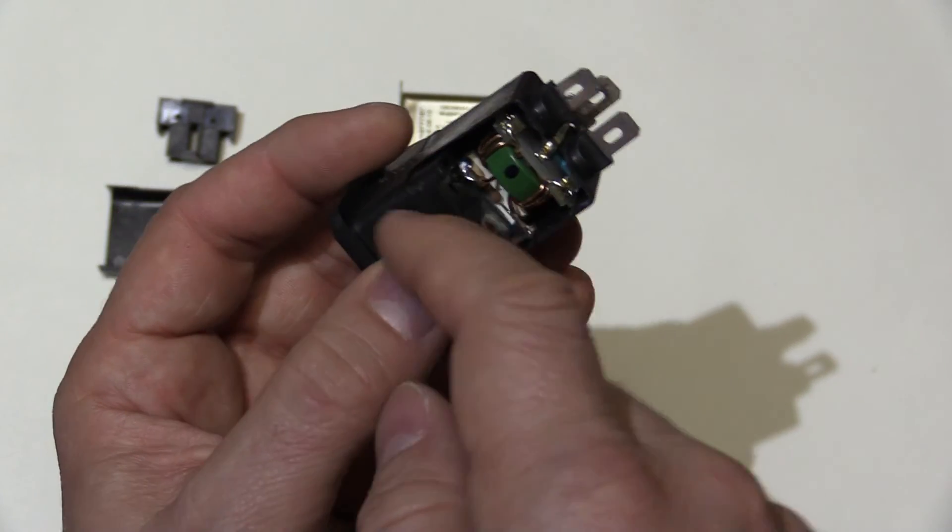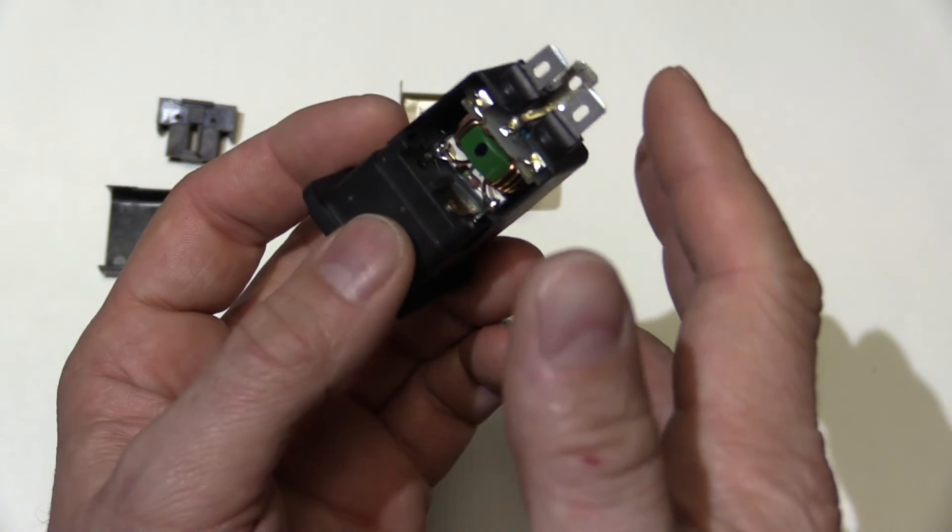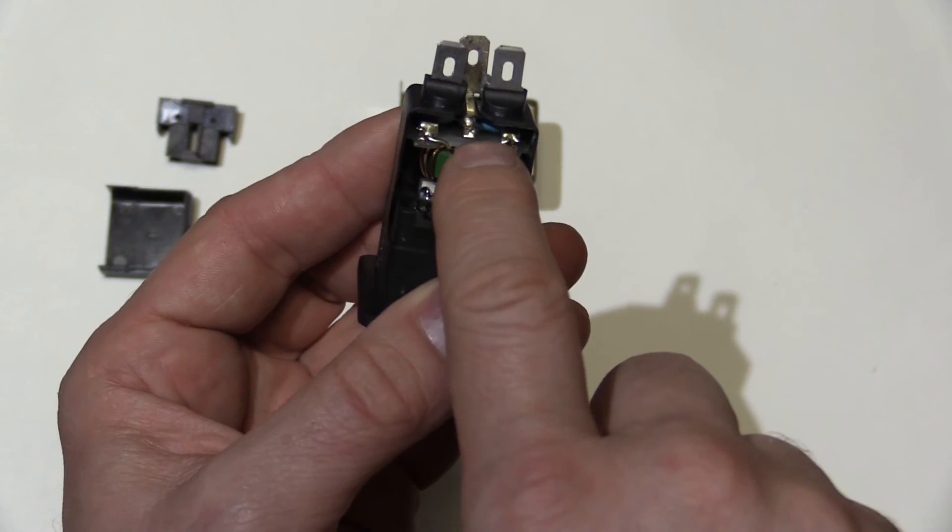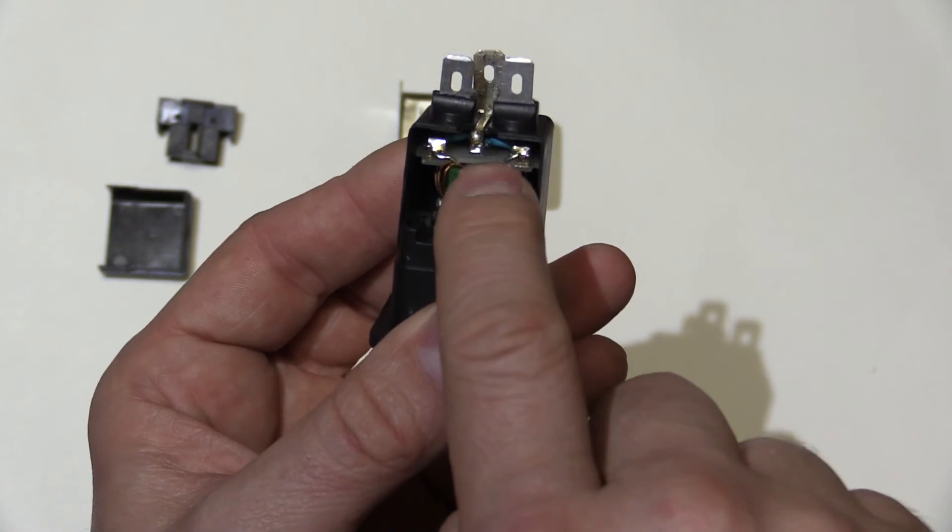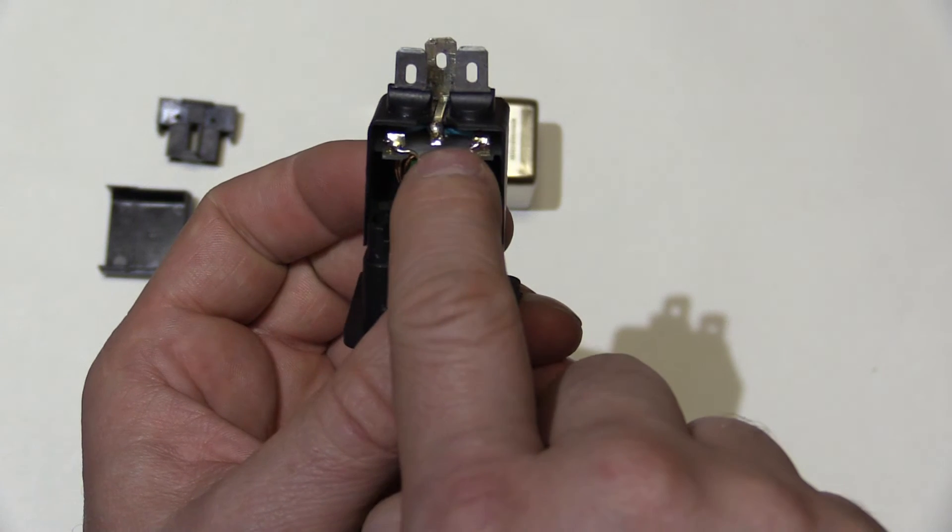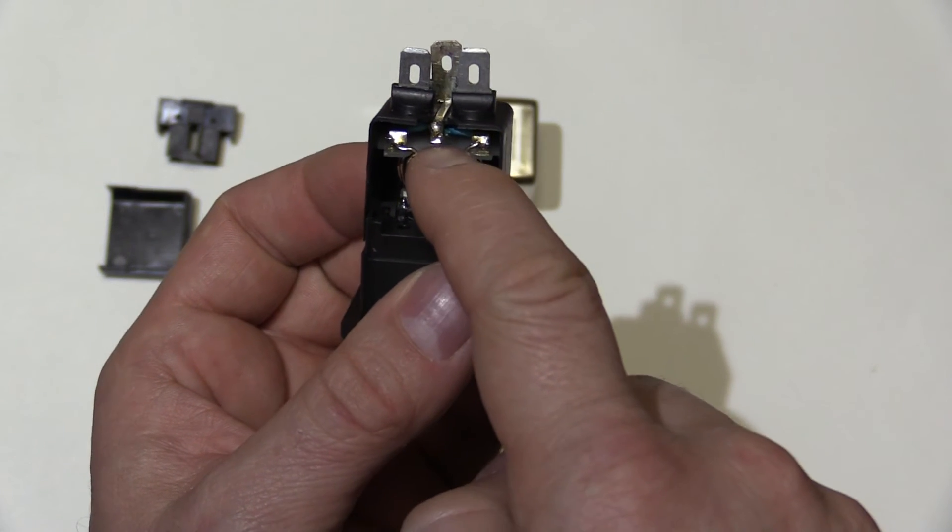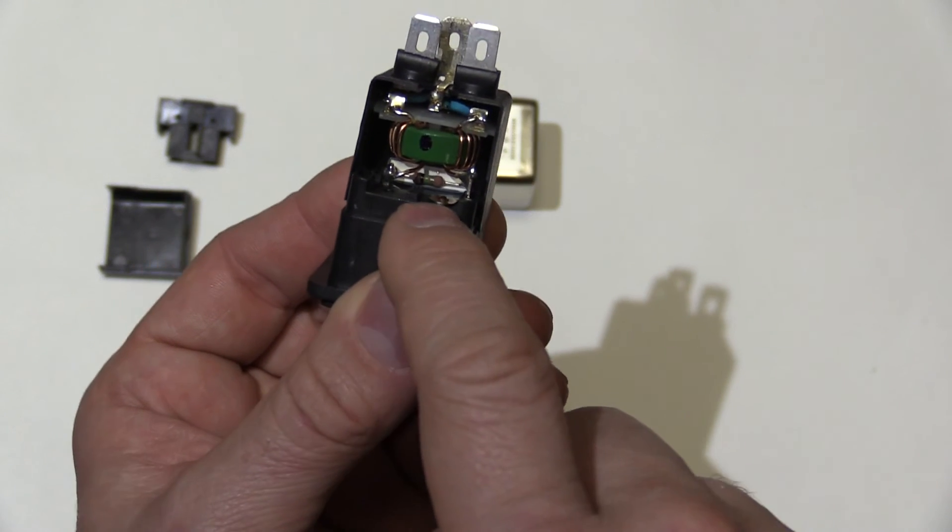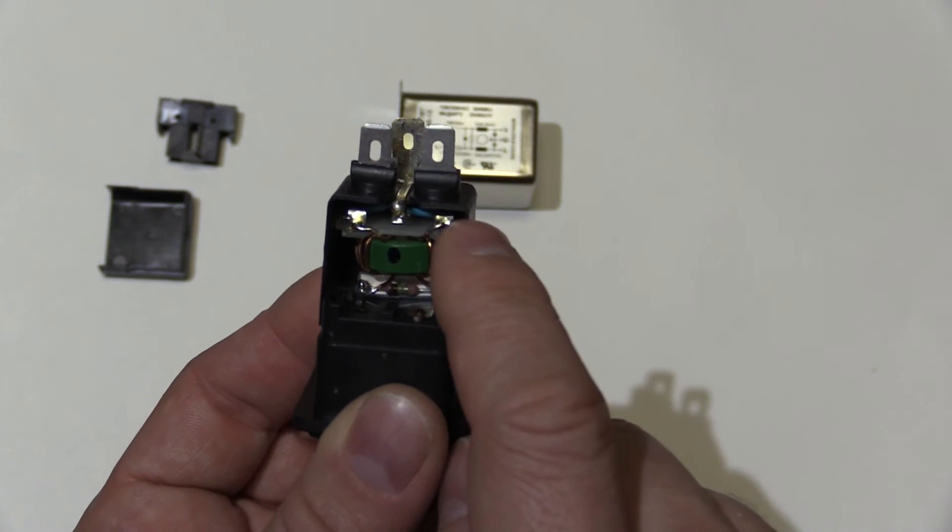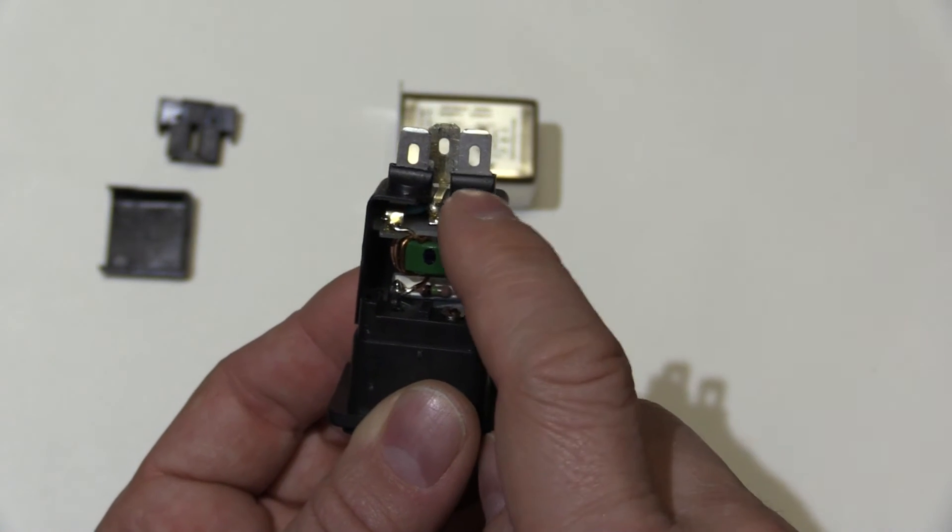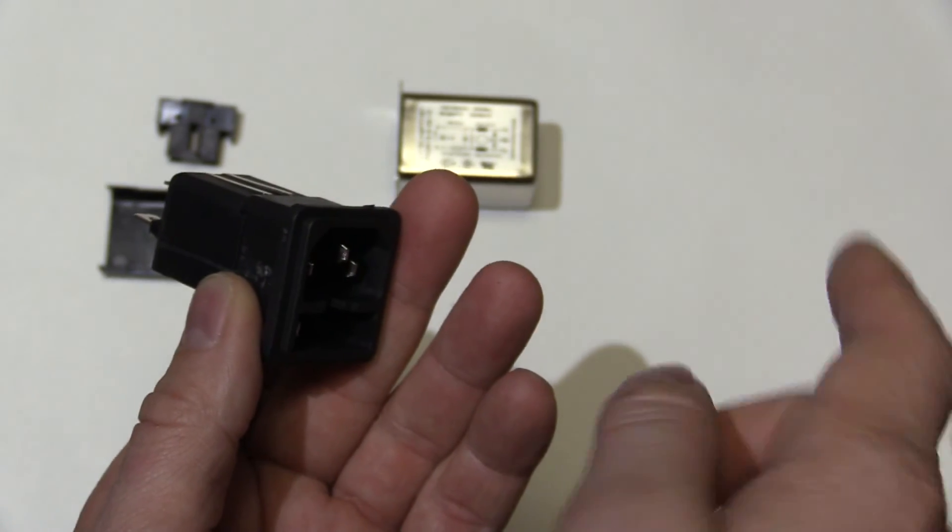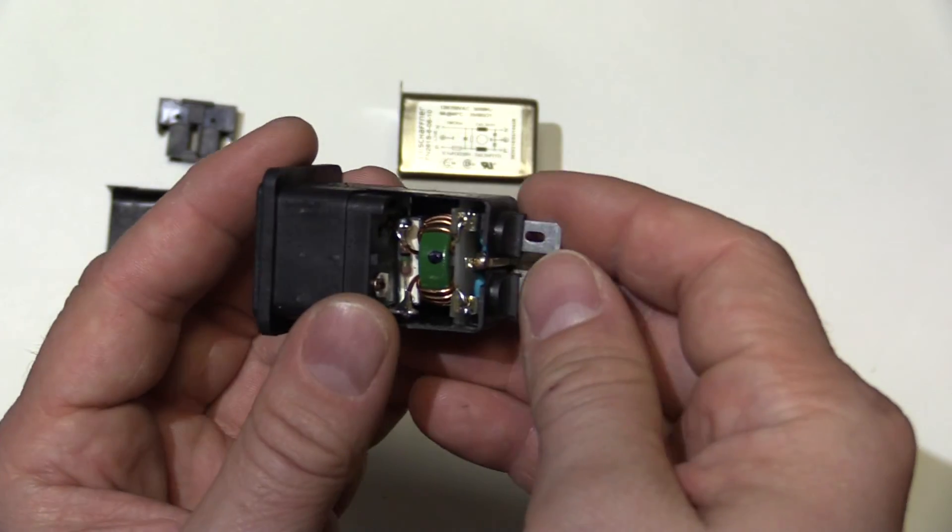So, the X class, if it fails, it'll blow a fuse, because it may fail short circuit. These ones will never, or should never fail short circuit. Because if they do, they're going to put voltage down to the earth. So what they do is, if they fail, they're designed to fail open circuit. But basically what they do, they do the same job as this first capacitor, except they're shunting any high frequency noise down to earth. So then it goes through your earth pin and just straight down into the ground through your building earth.